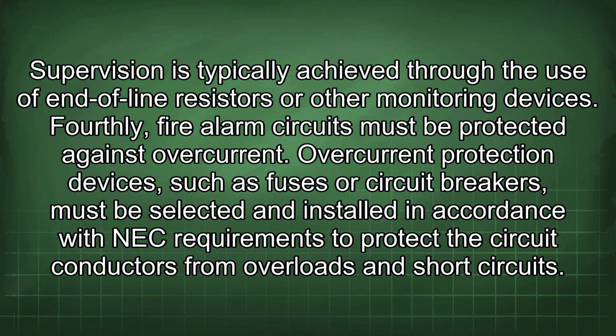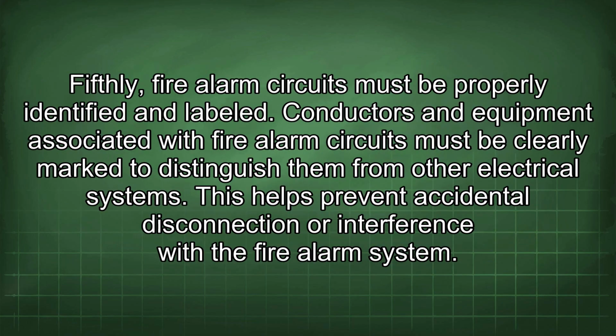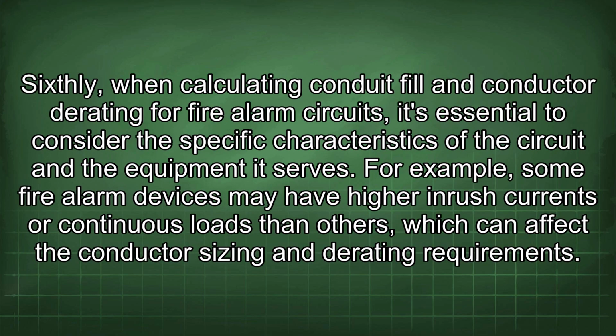Fourthly, fire alarm circuits must be protected against overcurrent. Overcurrent protection devices, such as fuses or circuit breakers, must be selected and installed in accordance with NEC requirements to protect the circuit conductors from overloads and short circuits. Fifthly, fire alarm circuits must be properly identified and labeled. Conductors and equipment associated with fire alarm circuits must be clearly marked to distinguish them from other electrical systems. This helps prevent accidental disconnection or interference with the fire alarm system. Sixthly, when calculating conduit fill and conductor derating for fire alarm circuits, it's essential to consider the specific characteristics of the circuit and the equipment it serves.